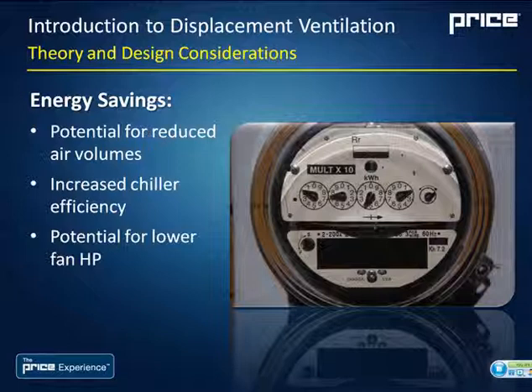Now the other point here is there's a potential for increased chiller efficiency because you're shifting your operative band up. With a typical mixed system, you'd see a supply temperature of 55 degrees off your coil, and your return temperature is going to be around 74, 75 degrees. So you're seeing a 20 degree delta T there. If you look at the displacement system, we see a 65 degree supply temperature, but there's still about a 20 degree delta T where you see return temperatures of around 80, 85 degrees up to 90 degrees. So by shifting that up in the operative band, your coefficient of performance on the chiller is actually increased.